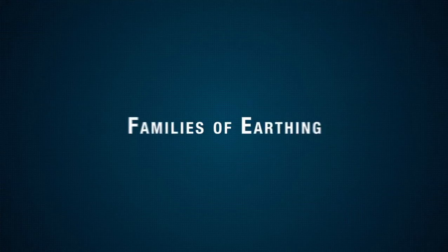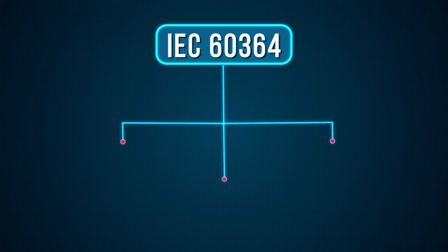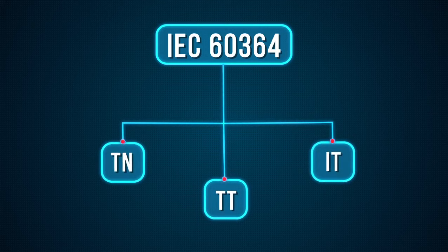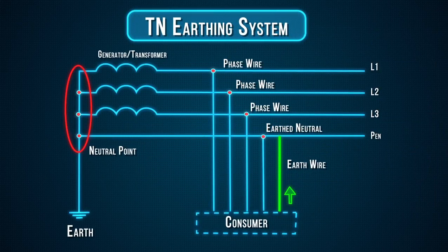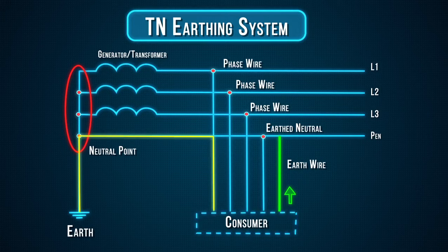Families of earthing. International Standard IEC 60364 distinguishes three families of earthing arrangements using the two-letter codes TN, TT, and IT. In a TN earthing system, one of the points in the generator or transformer is connected with earth, usually the star point in a three-phase system. The body of the electrical device is connected with earth via this earth connection at the transformer.